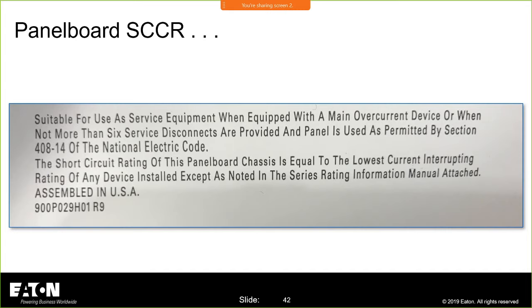So imagine you did it all right on installation. Every interrupting rating of every breaker in that panel board is 22K. The short circuit current rating of that equipment is 22K.